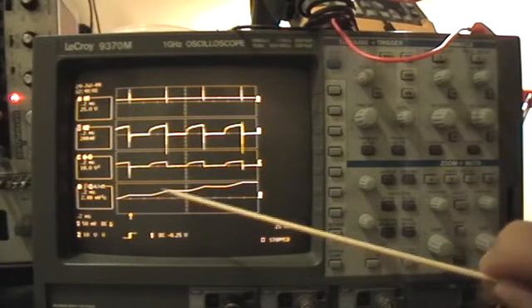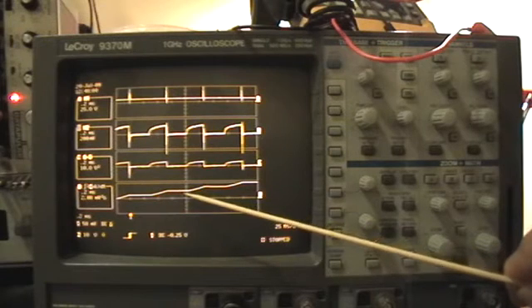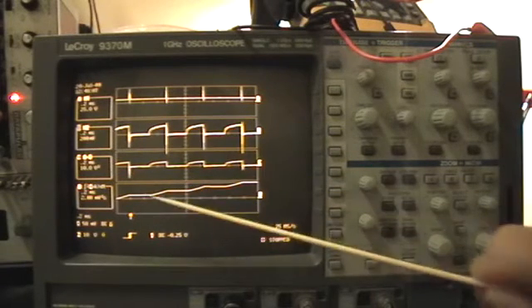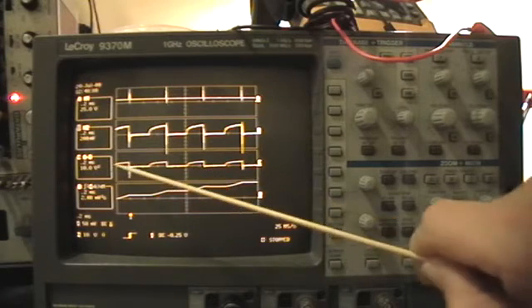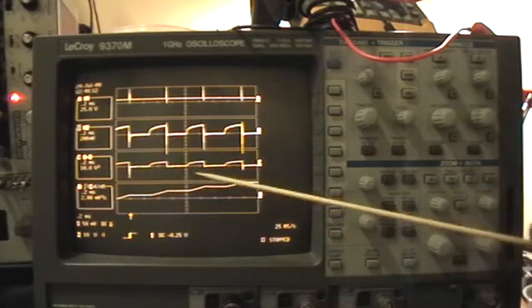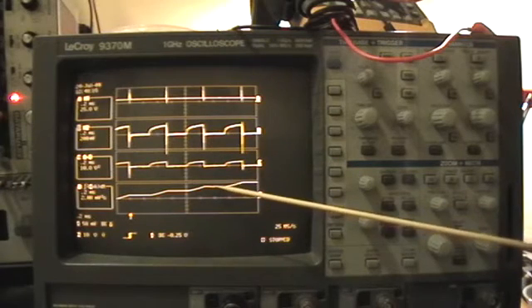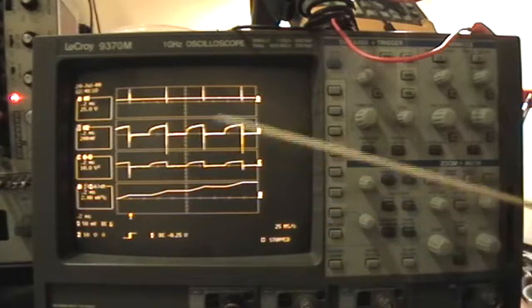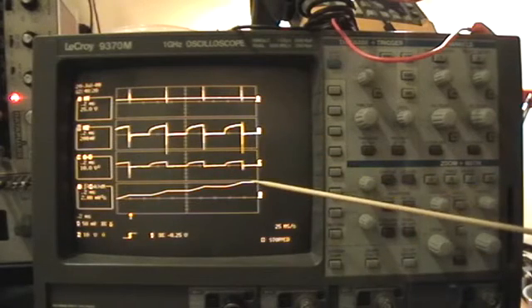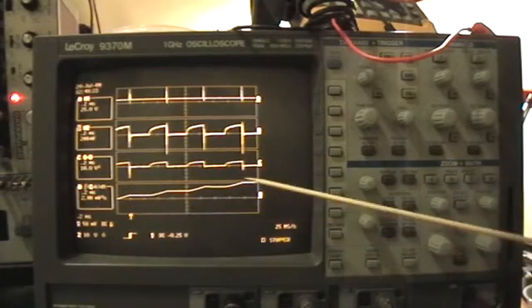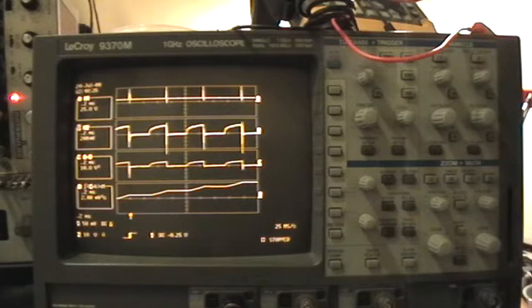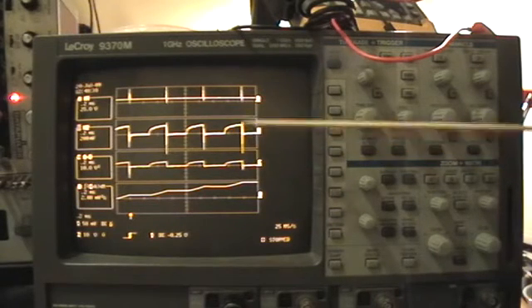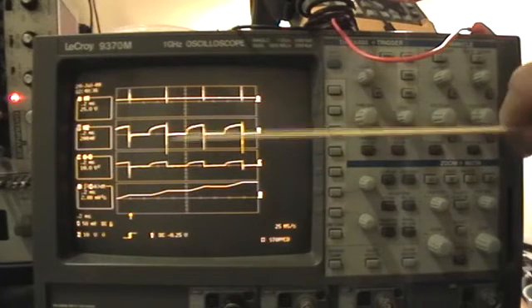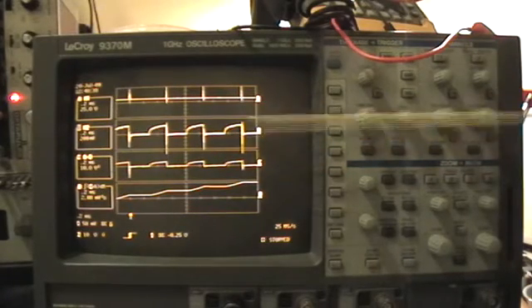And this curve here, if you just read whatever the value is of the point at that particular time, that gives you the total energy that has flowed from zero time, wherever your trace starts, to that particular time that you have of interest. So now you take a known number of cycles, say 1, 2, 3, 4, read right there, that is the energy transferred over 4 cycles, and then you multiply that by the number of cycles in the time period of interest, and you have the energy flow. And that takes into account all of the reversals and whatever happens in the spikes.